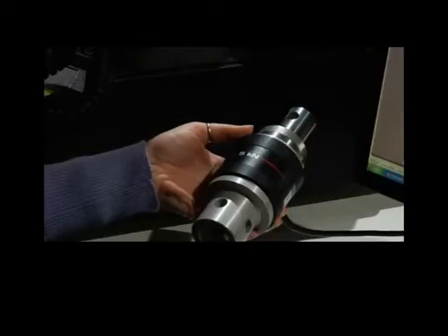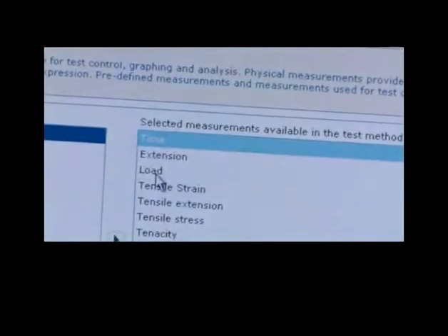Bluehill 3 can be configured to require that a specific load cell or extensometer be used for particular tests. If that device is not connected, or a different device is connected, the test will not start.